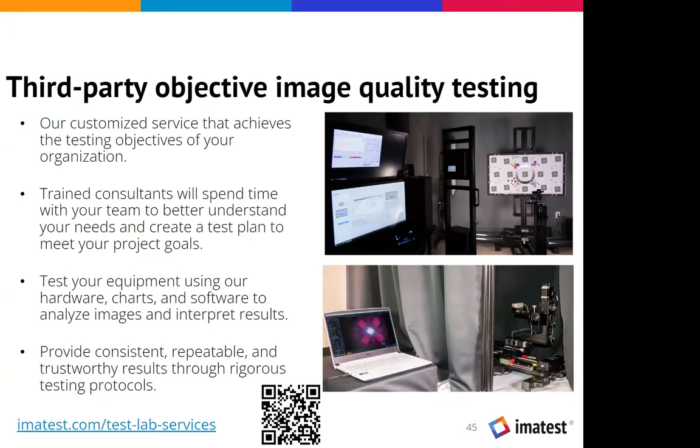Also test validation. So customers that were performing their own testing and had some questions about the procedures and the results sent us one of their devices so they could compare our results to theirs. And that was very helpful for them. Production tolerances: customers will send us 10, 15, 20, 30 devices, and we will basically create a list of tolerances for those sort of pass-fail metrics for their devices.